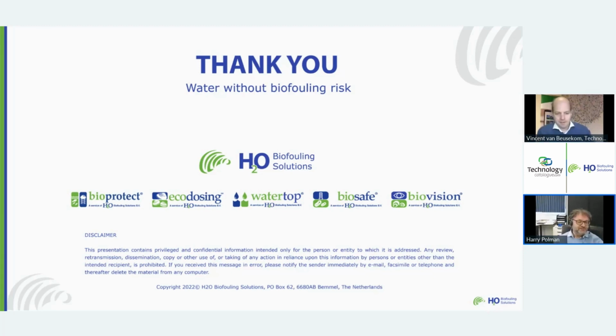Well, it is very case dependent, but these are projects we have executed in the past, and the first step will be a risk assessment. So get insight into the type and amount of fouling in the system, and whether there is filtration, like mussel filters in front of the heat exchanger, which could remove debris. This gives an overall assessment of what is in the system and what the risk could be when this is released to the utility.